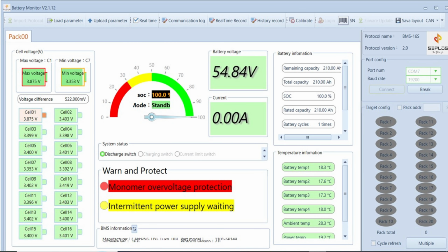At some point between midnight and 6:21 a.m., Cell01 reached its overvoltage threshold and the BMS stopped charging. When I checked the pack in the morning, this is what I found. Cell 1 at 3.875 volts. Pack voltage 54.84 volts. Other 15 cells sitting between 3.35 and 3.42 volts.